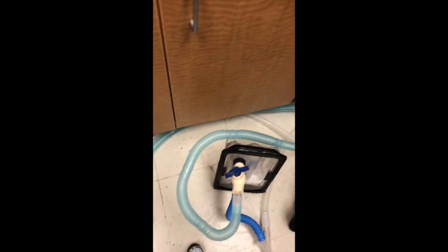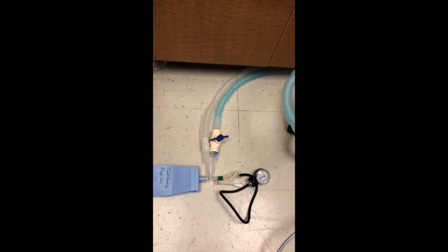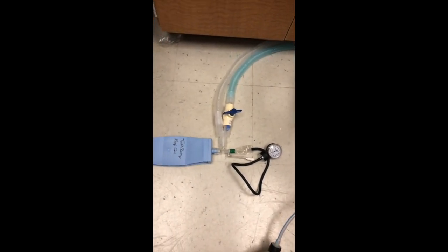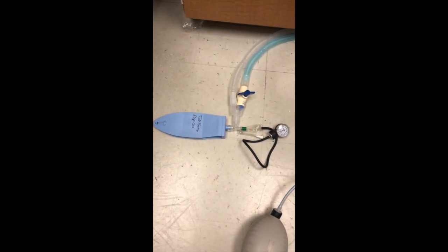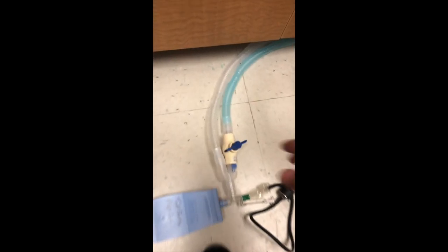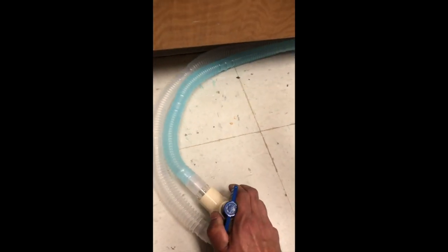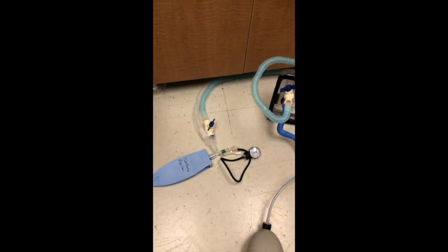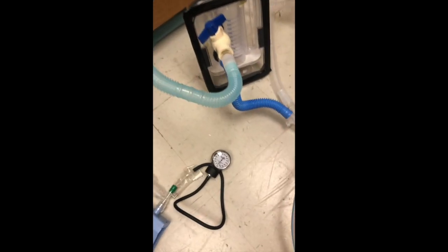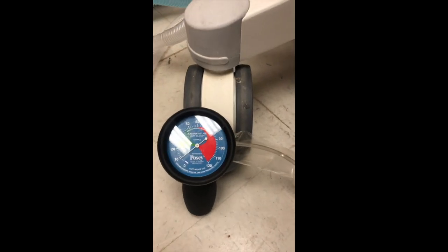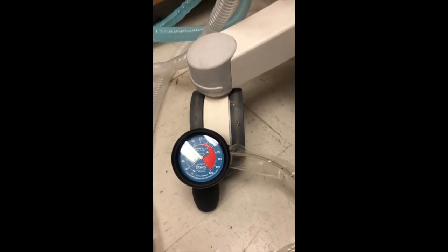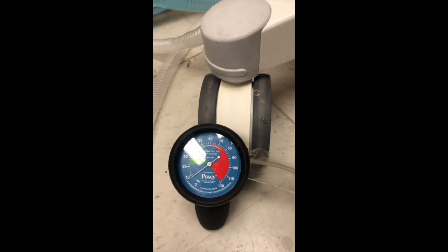By modifying the ventilator with supplies readily available in the hospital, with the exception of a ball valve, which is readily available in any hardware or plumbing store, most ventilators can be modified to ventilate multiple patients with individualized pressure or volume and even PEEP. Please refer to my previous video for detailed instructions on how to set up the spirometer and other connections for measurement of volume, etc. The blue lines denote the inspiratory limb, and the white lines usually denote the expiratory limb.